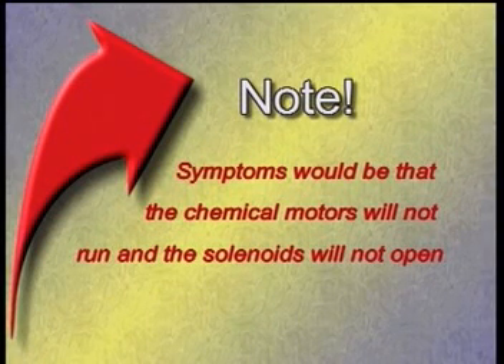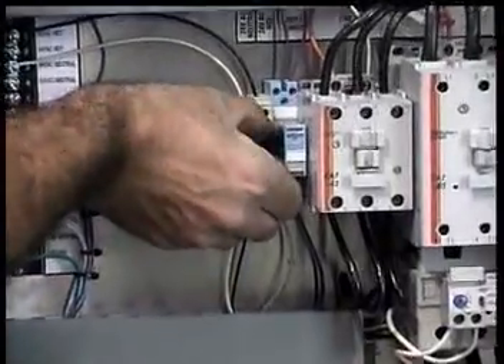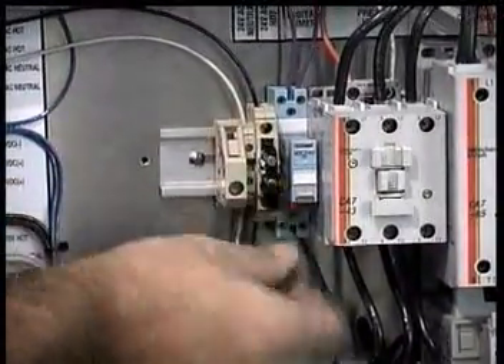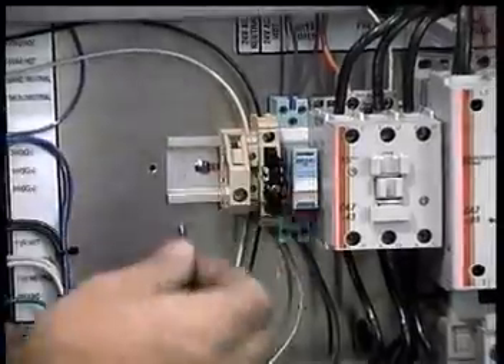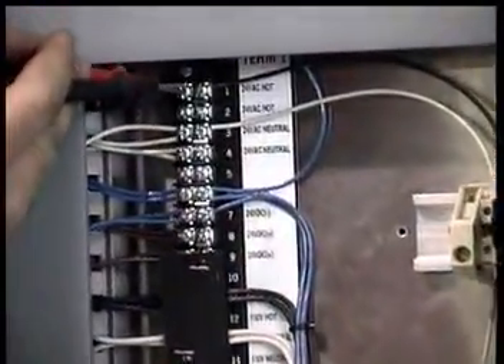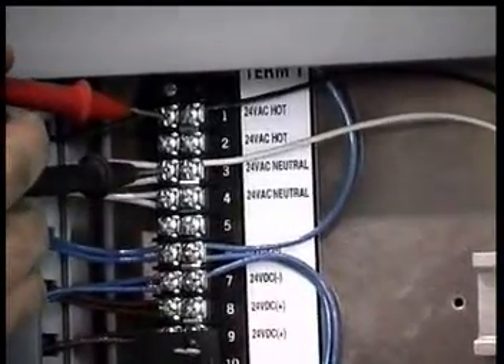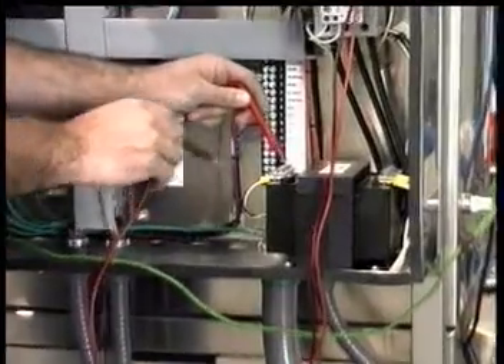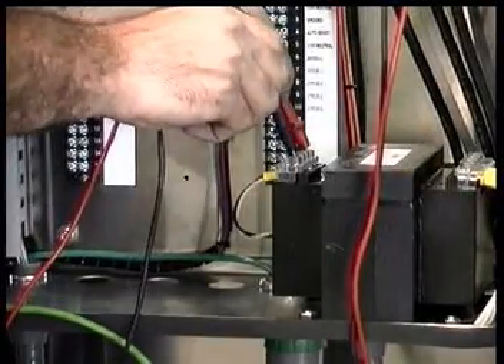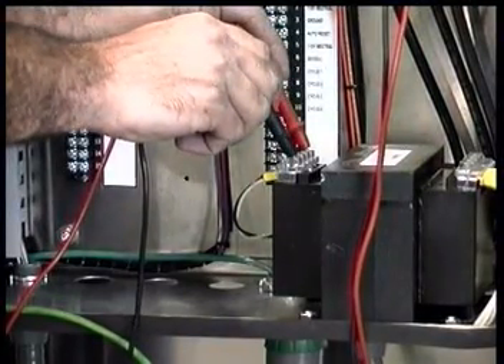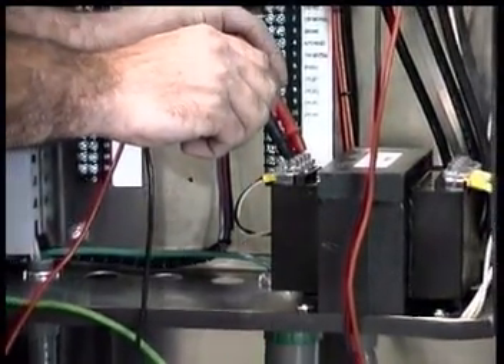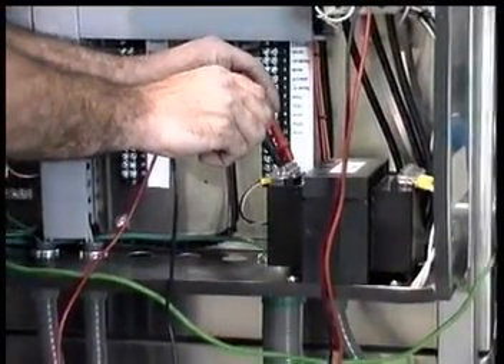Symptoms would be that the chemical motors will not run and the solenoids will not open. Begin by checking the 24 volt fuse to the left of the spot-free rinse relay. If the fuse is okay, check for 24 volt power between terminals 1 and 3 on terminal strip number 1. If no voltage is present, check for power on terminals X1 and X2 on the transformer. Verify that the transformer has 110 volt power to it.